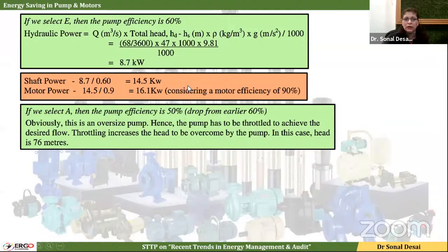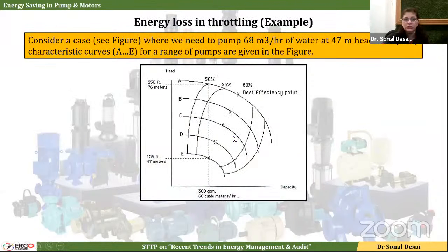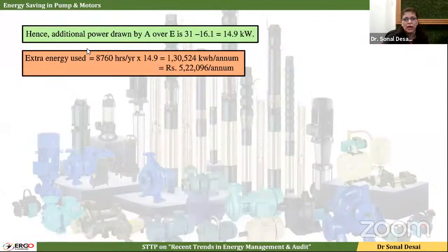So the choice is yours. When we have pump E selected, this is its consumption, and when we have pump A selected, this is its consumption. The comparison shows that when we have pump A selected, it will draw 31, while when we select pump E, it will draw just 16 kilowatt. We are saving 14.9 kilowatt. Per year, we are saving 1,30,000 units. Yes, 1,30,000. If you just multiply, this is with the minimum utility rate taken. If you consider 7 rupees, then it will be even larger than this. 7 to 8 lakh of rupees we are spending because of selection on the higher side. So initially we have invested more. That is the first mistake. Then we are continuously investing more by running with higher electricity. That is the second mistake.